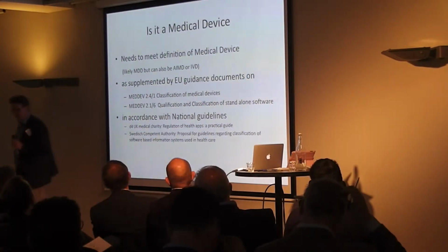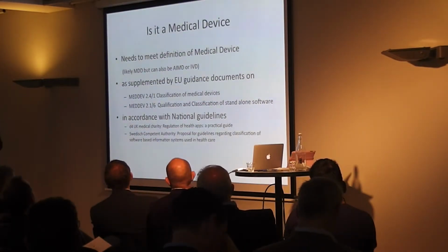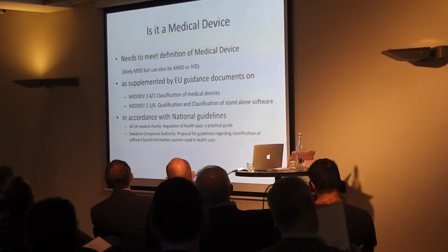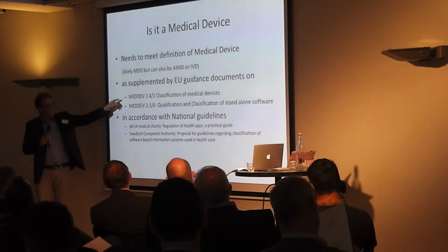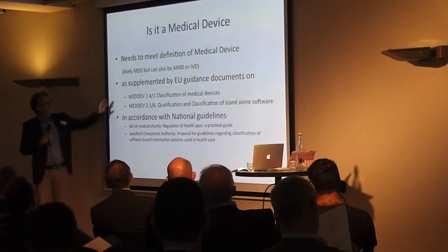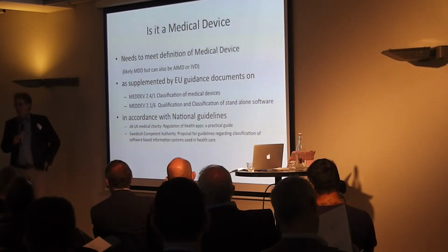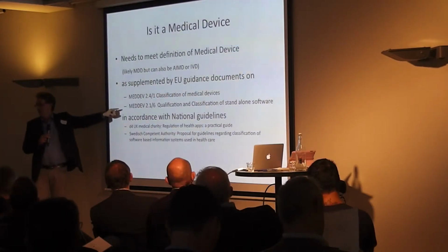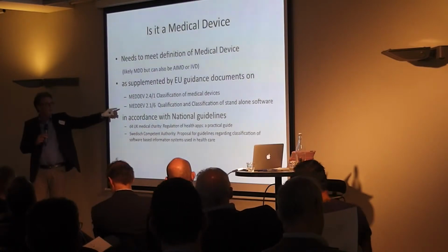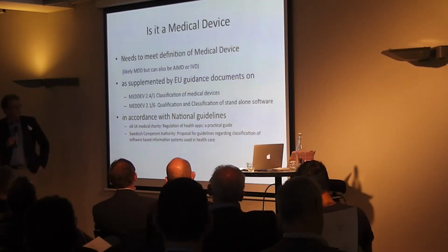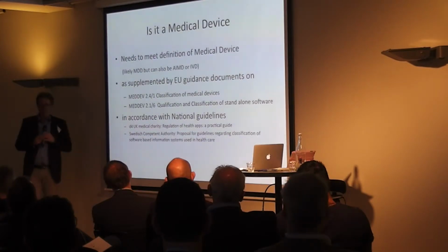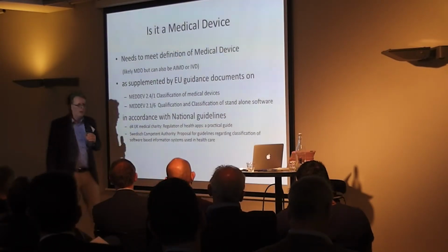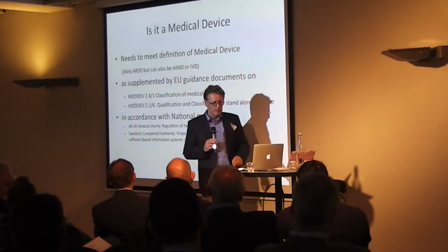At least it has to meet the definition of a medical device, as supplemented with the guidance, the MEDDEV guidance documents. They give you more insight into how it actually works and how different exams are needed. The directive gives a general description, sometimes difficult to interpret. These guidance documents really help you out in deciding: is it a medical device? And in the case of standalone software, does it qualify as standalone software? And of course you have these additional guidance documents, which you can check on the blog of Eric, and he will keep you updated on that.